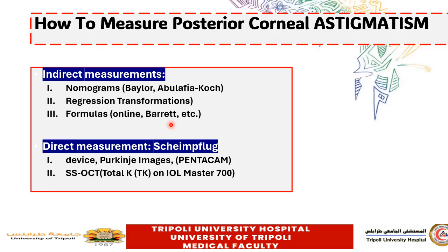The direct measurement way is using Scheimpflug technology like the Pentacam, or using swept source OCT like the IOL Master 700, which measures the TK, which is the total keratometry power. So this is a direct measurement of the posterior corneal astigmatism.